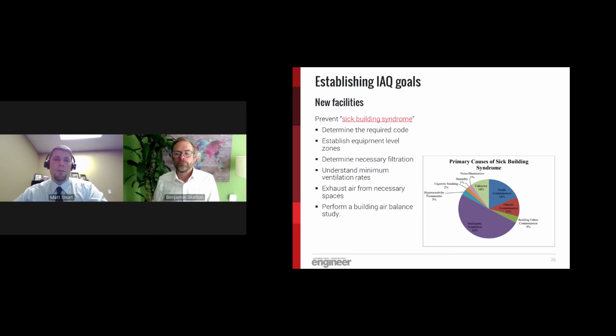These three items alone make up approximately 80% of the most common causes of sick building syndrome. To prevent this, designers should consider some of the following steps when beginning the design of any new facility. First, determine the required codes and establish the minimum criteria from the most stringent code that applies. This will help create a ventilation baseline for the facility.